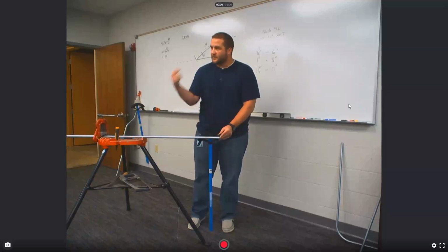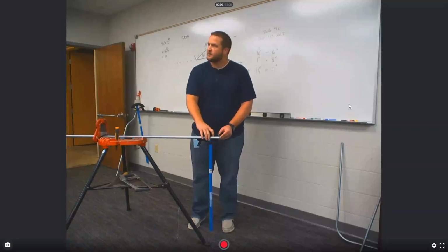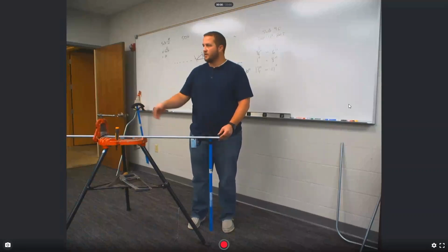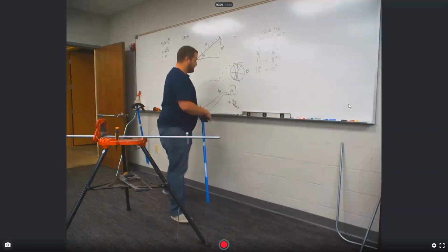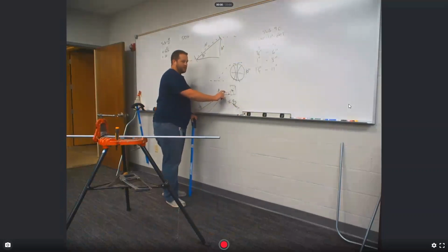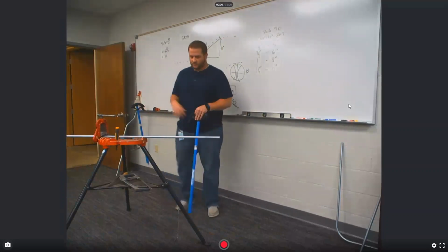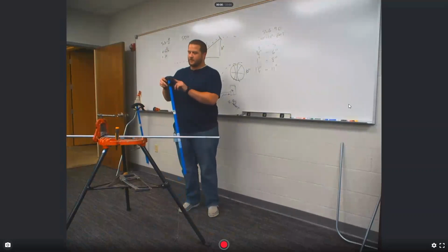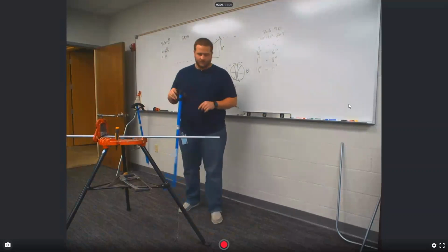But I have a standard in my head. What I always use when I'm bending conduit is I come out 2 inches. That's just my standard. You could make it 1 inch, 1.5 inches, whatever you want. You just come out a little bit. It doesn't really matter, but there needs to be a little bit of a flat space right there before you start the bend. Otherwise, you're not going to be able to fit the pipe in the chute.